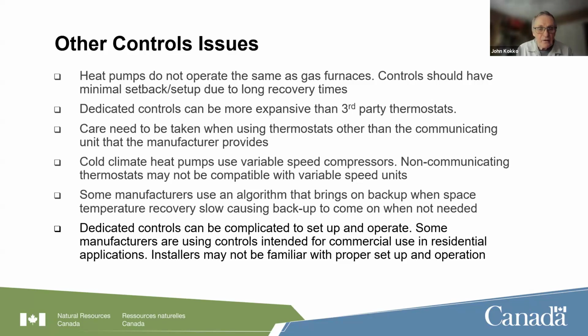Although I am seeing some heat pumps that will do variable speed, it's based on an algorithm built into the unit and uses its own outdoor air thermostat to provide that variable speed control. And so it's not necessarily going to give you the same performance as the dedicated communicating thermostat that comes from the manufacturers.